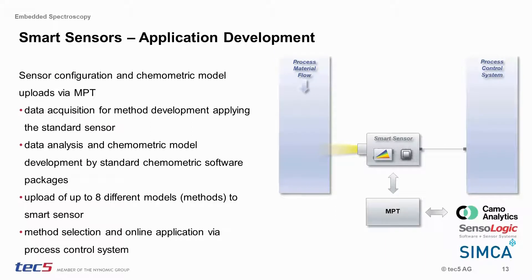In order to immediately convert measured spectra into process-relevant and manageable data, our smart sensor systems have to be trained and configured accordingly. The monitoring and parameterization tool, MPT, is the key element for sensor configuration and upload of up to eight chemometric models to the embedded electronics. For this so-called application development, spectra can be acquired for standard multivariate data analysis packages from known suppliers like Camo Analytics, SensoLogic, and Umetrics SIMCA. Once the chemometric models are finished, they can subsequently be transferred to the smart sensors via service ports. Our smart sensor systems are also capable of receiving relevant data such as recipes through a PLC.